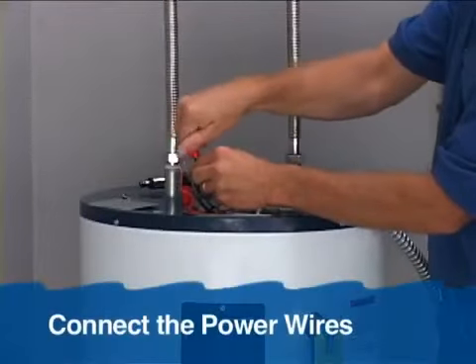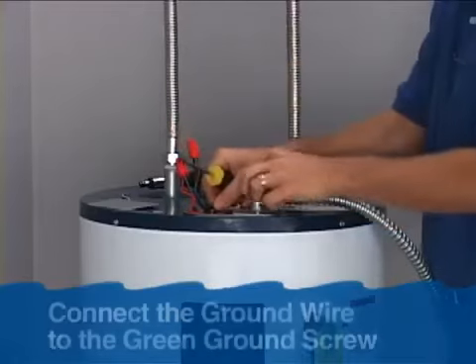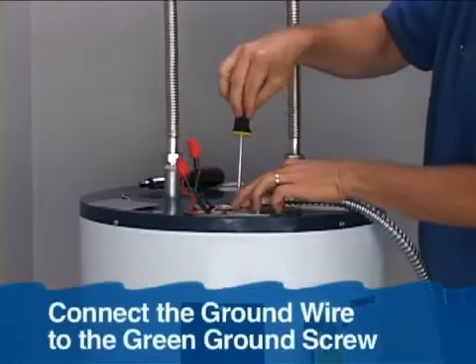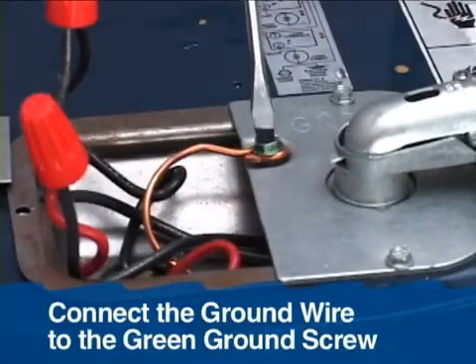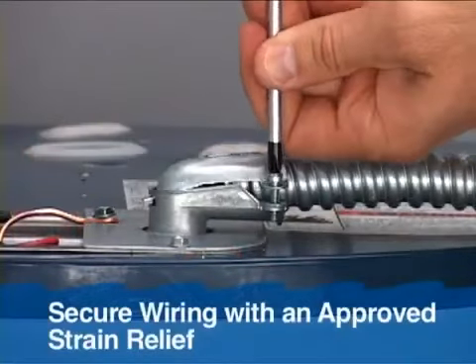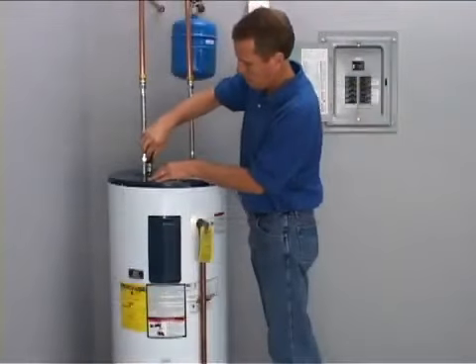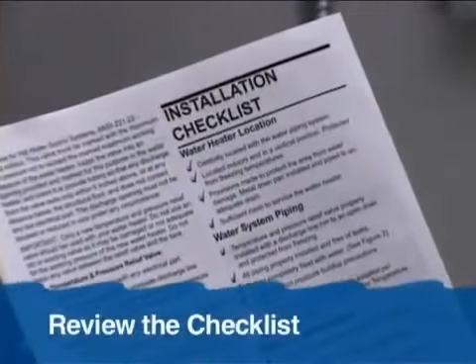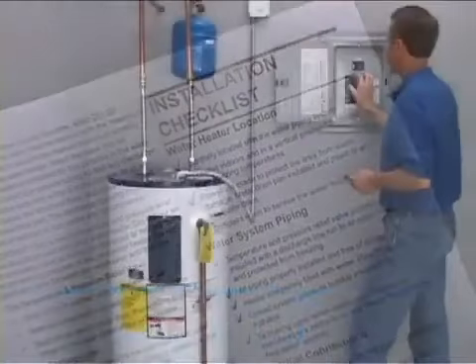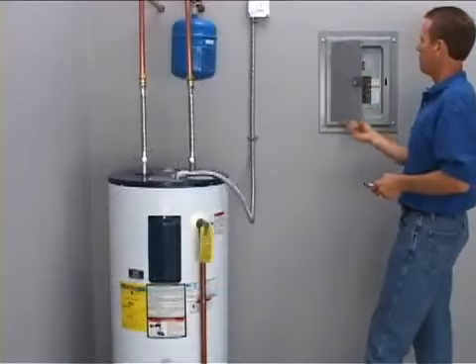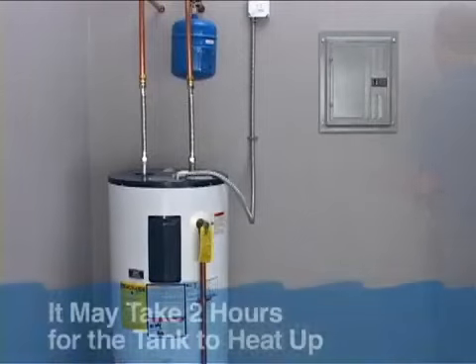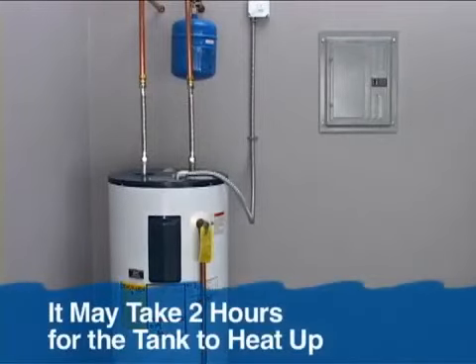Next, connect the power wires and ground wire. The green or copper ground wire must be connected to the green ground screw. Secure the wiring with an approved strain relief. Replace the cover on the junction box. Review the checklist in the installation instructions. Now turn electric power back on. With a tank of cold water, it will take several hours for the water to heat up.